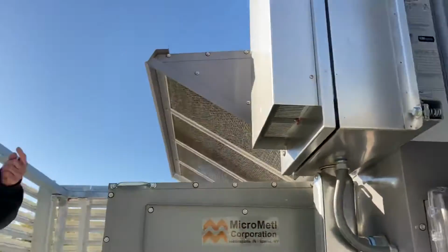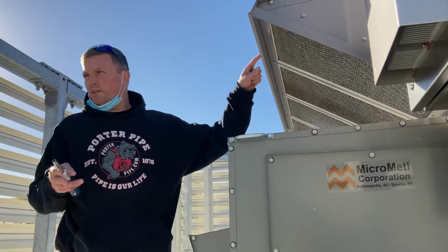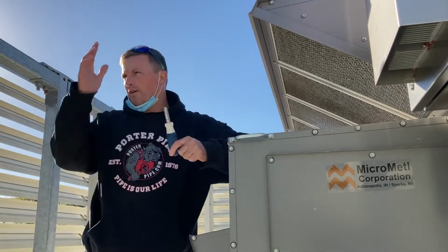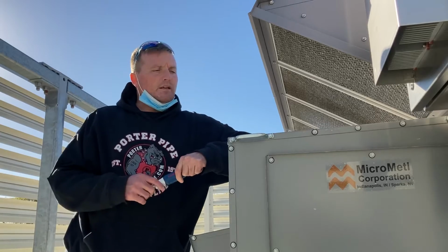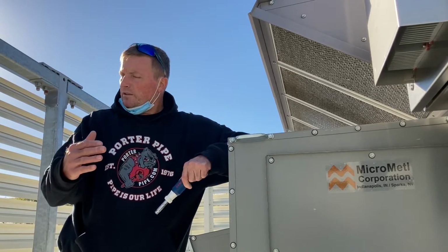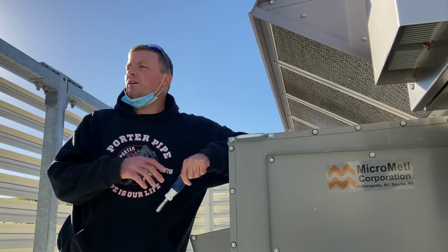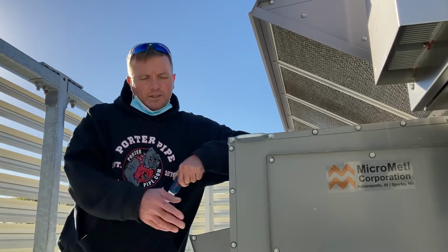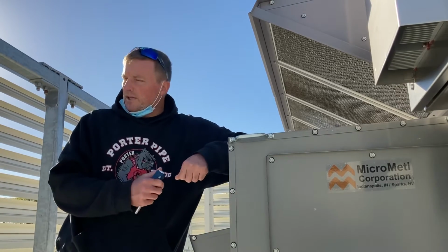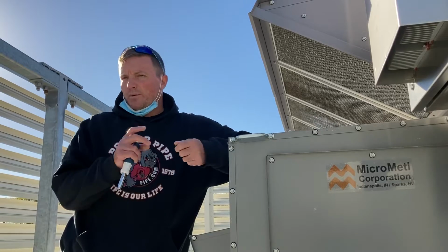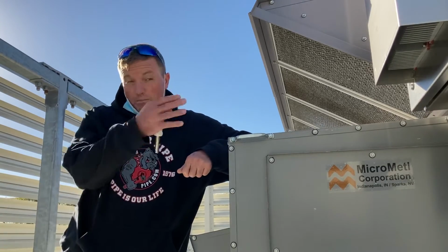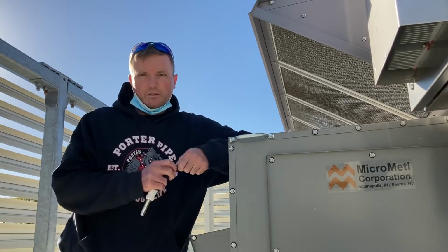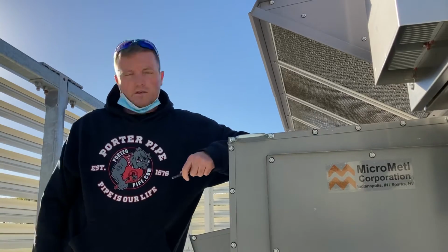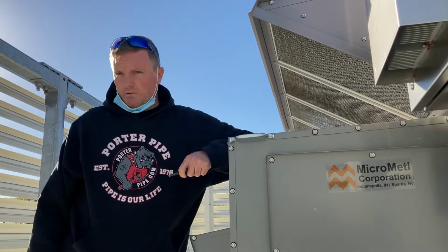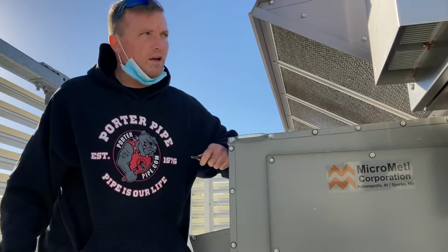So if we have economizer, meaning free cooling, basically less than 55 degrees outside, the fresh air will come in to make cooling. If the building pressure becomes over pressurized, we turn our exhaust on. That's not going to happen unless they're doing something different, because there's no building pressure transducer in there. So we need to make sure we get you set up, or we need to figure out what's up with that. So I'll take notes on this and I'll get with you guys on it.